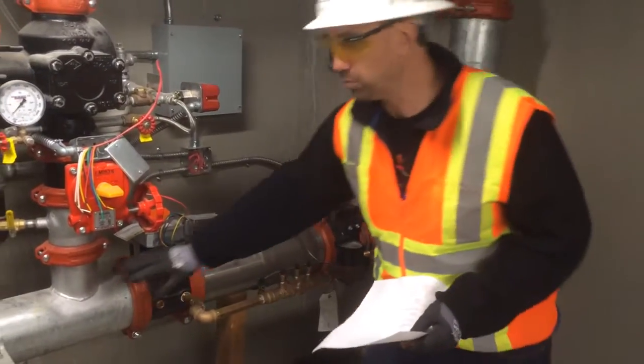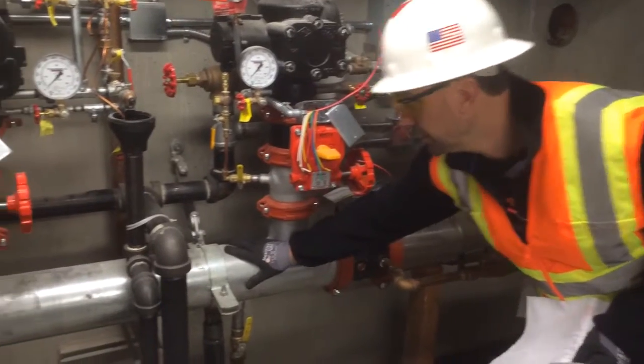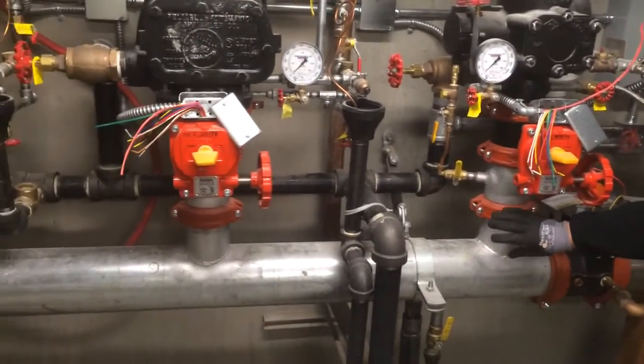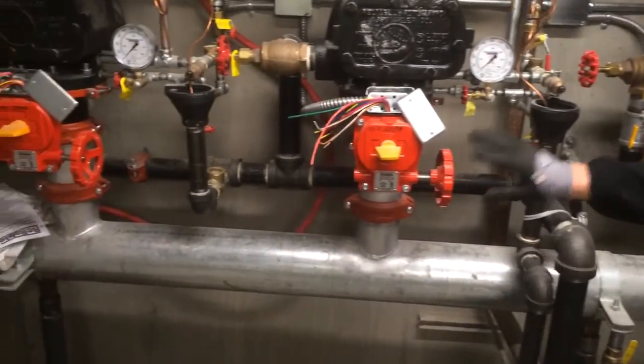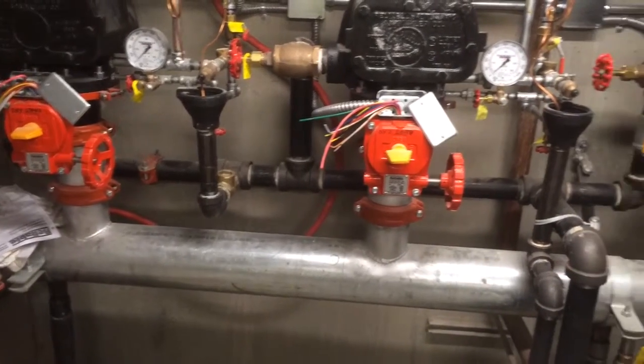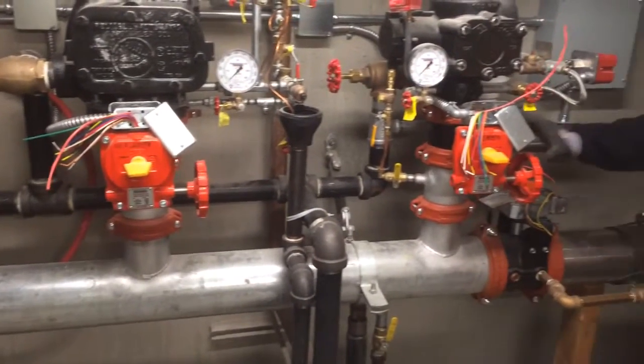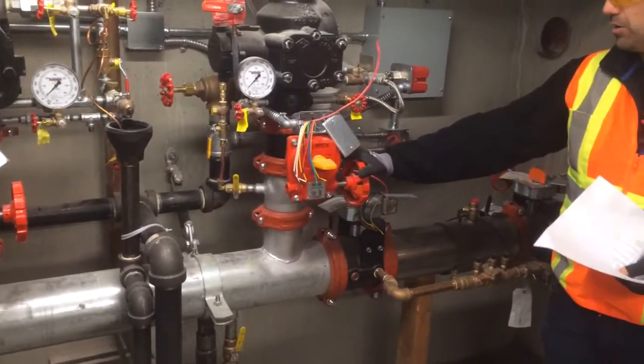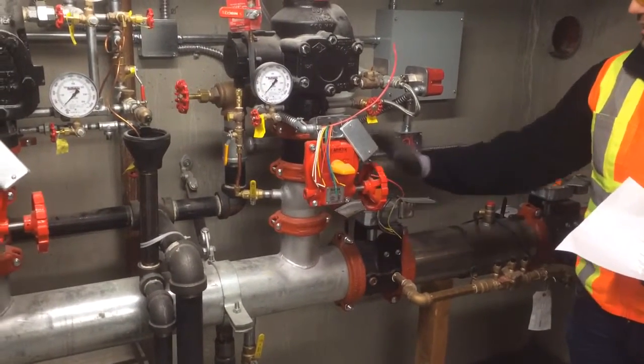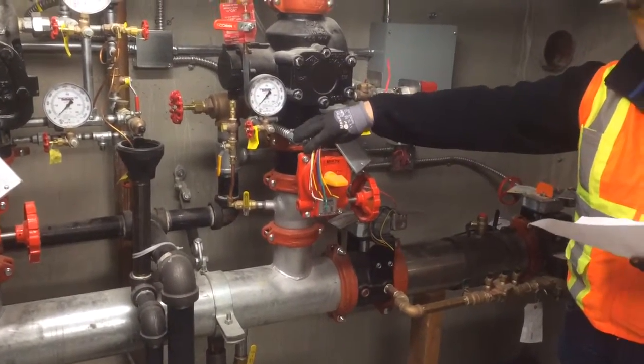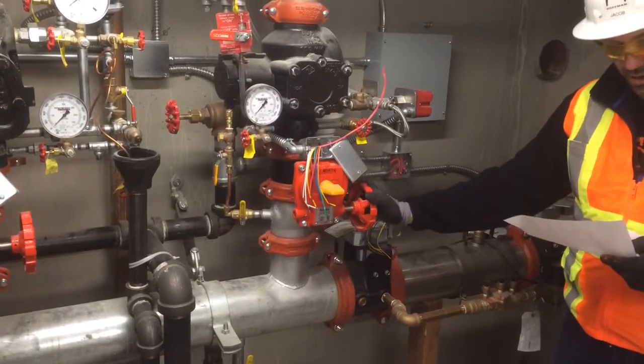It will have a manifold. That's this piece right here. This manifold distributes to each of the different zones. There's 3 zones in this system here. Each zone will have an isolation valve. And again, every isolation valve on a sprinkler system will have a tamper switch that tells the fire alarm when this has been turned off.